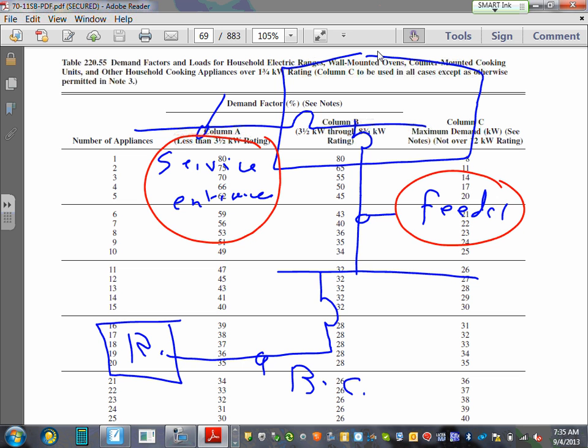With some exceptions, the branch circuits. Any comments, any questions, guys, about sizing? What is this table doing? It's sizing the services, the conductors coming to your building, as well as the feeders distributing the power to your building, and applying a demand factor.